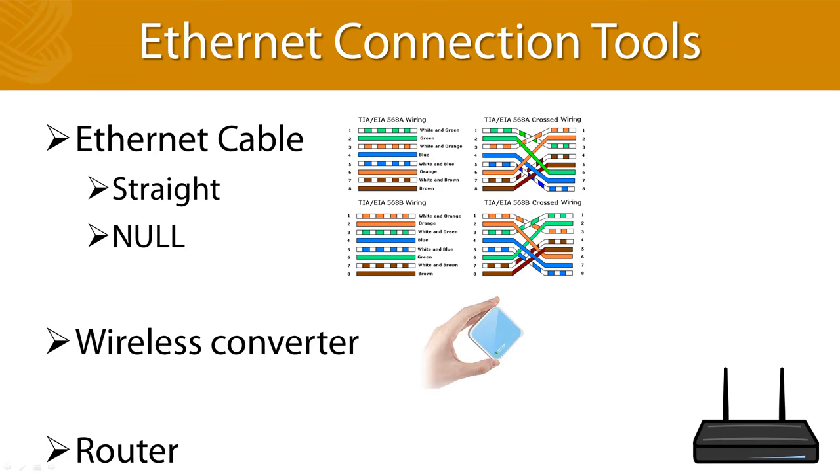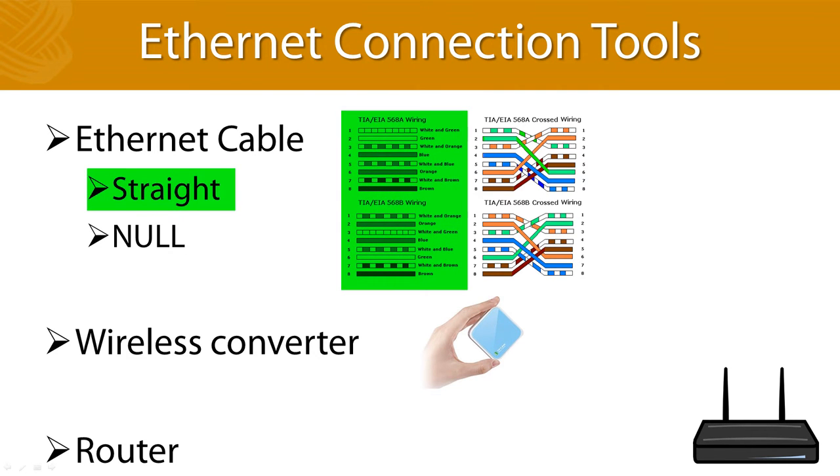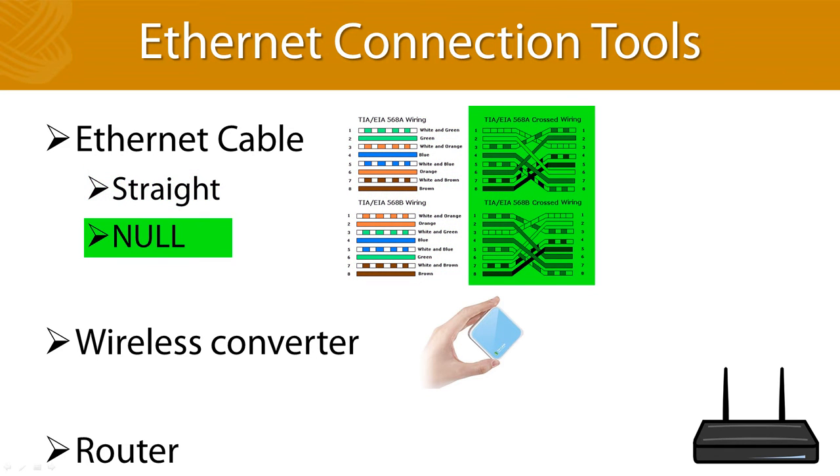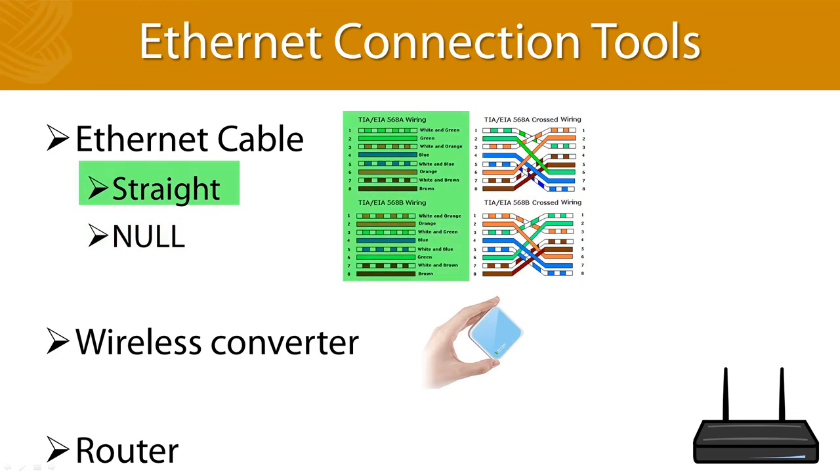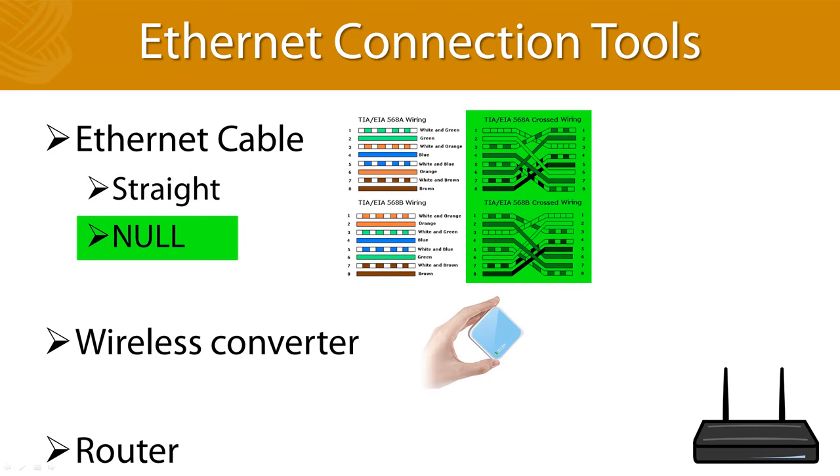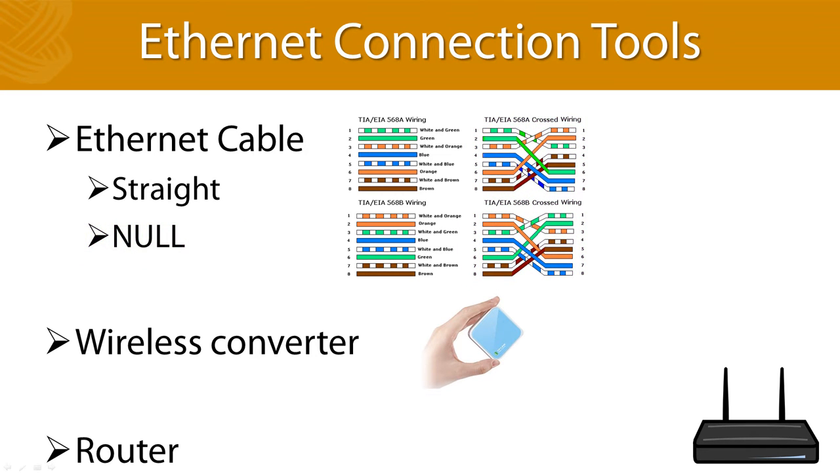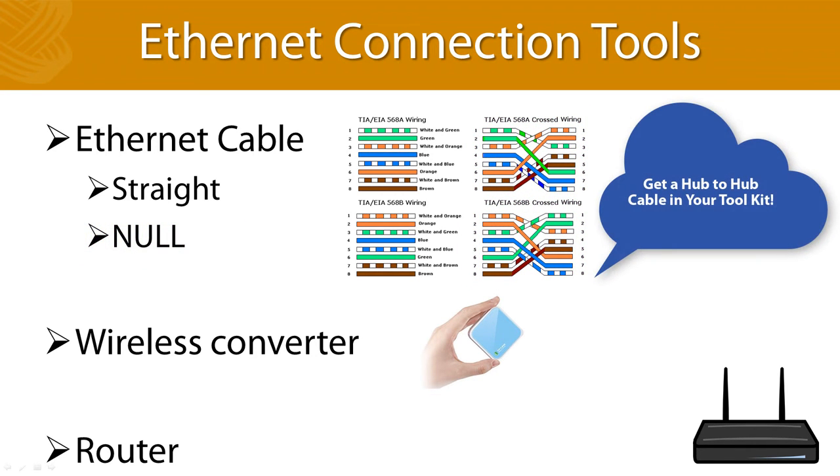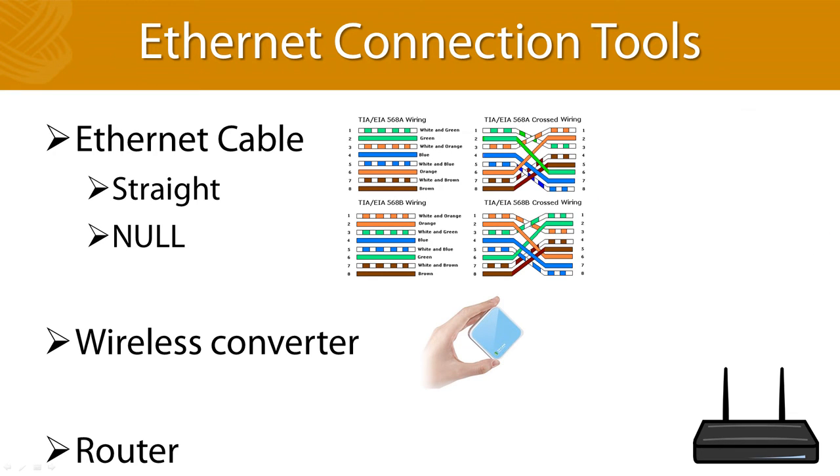There are two types of ethernet cables, just like in serial communication, but everything in ethernet communication travels in pairs instead of individual conductors. All of the pairs are connected to the same connector numbers in a straight through cable and pairs are crossed in a null modem arrangement. Straight cables are everywhere because they are the cables that connect your laptop to the office or hotel LAN when the Wi-Fi sucks. Null cables can only be purchased in a specialty store and are usually labeled hub-to-hub cables, so make sure you have one in your toolkit before you need it because it can be difficult to find on short notice.